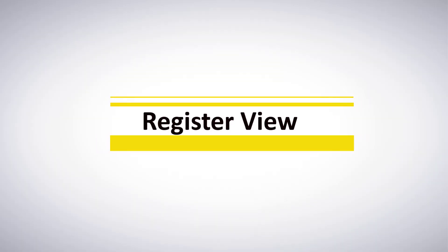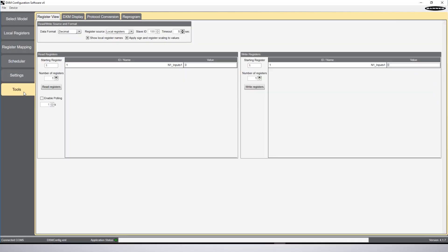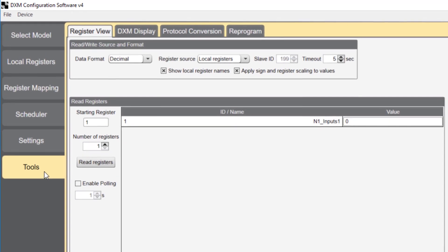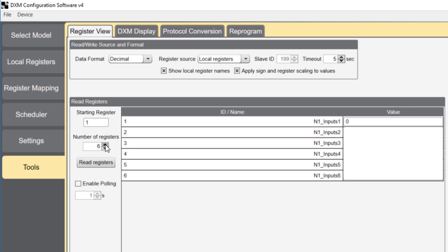This brings us to register view. You'll find register view under tools. This is where you ensure the data you set up with the read rule is being read into the local registers. Starting at register 1, I'm going to read the 6 registers we just set up. Click enable polling, then begin polling. This tells the gateway to automatically pull data from the connected node. When node 1 input 1 is activated, it registers in local register 1. Now we know the read rule is working correctly.